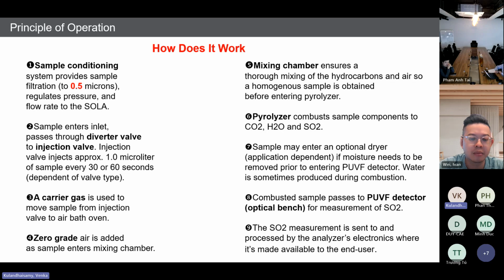The injection valve, every 30 seconds, injects a 1 microliter sample into the pyrolyzer assembly, which is the burner assembly. This 1 microliter sample is carried over by a carrier gas. The carrier gas can be nitrogen or instrument air. For most diesel applications, we have to use nitrogen as the carrier. For all other applications, we use clean zero grade air as the carrier gas. So the carrier will carry the 1 microliter sample to the pyrolyzer assembly.